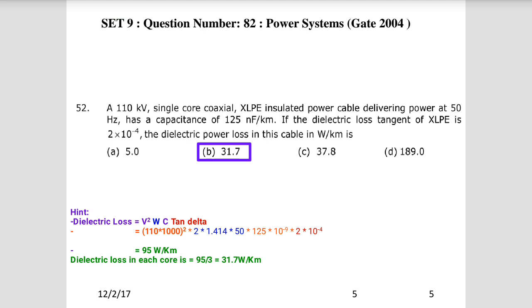In this question, the voltage of the system, the capacitance, and the dielectric loss tangent are all given. Using dielectric loss = V²ωC tan δ, with V = 110 kV, ω = 2πf, and substituting tan δ, then dividing by 3 for each core gives the answer: 31.7 watt per kilometer.